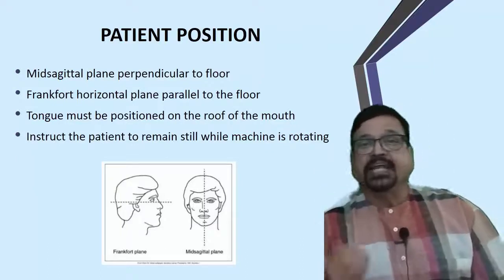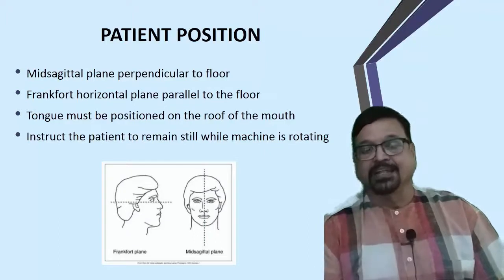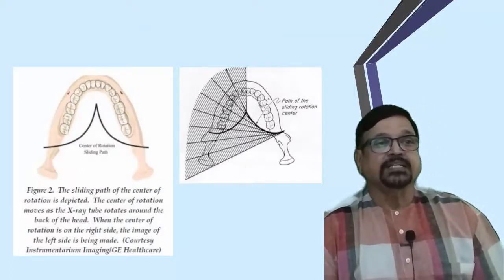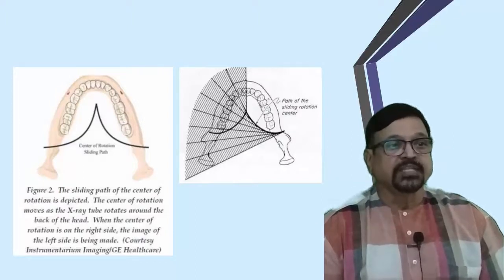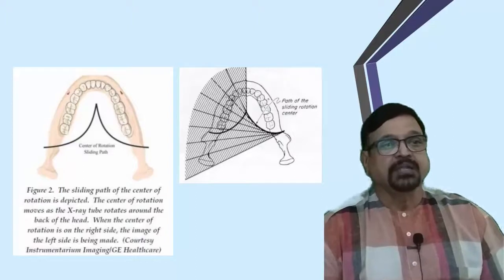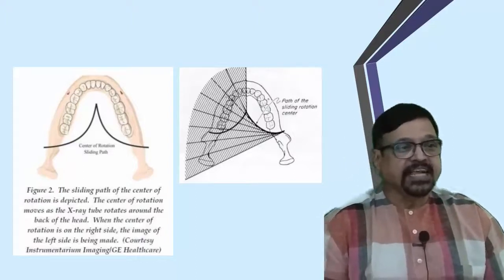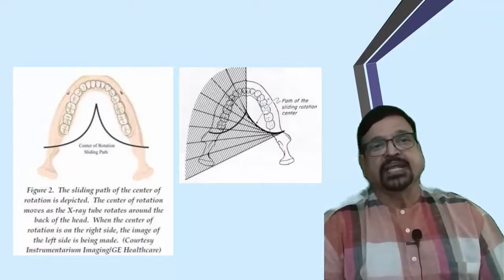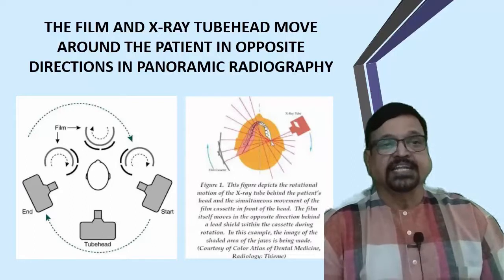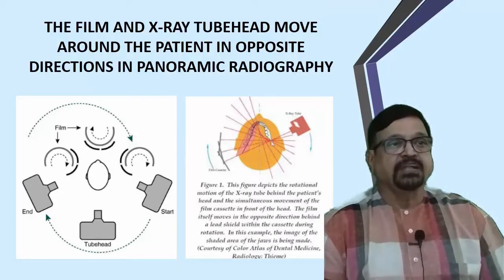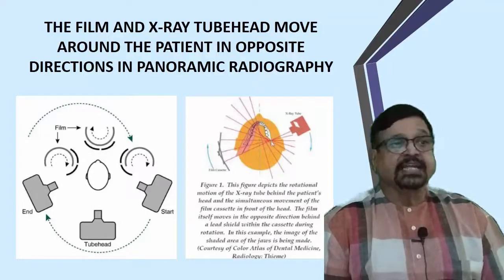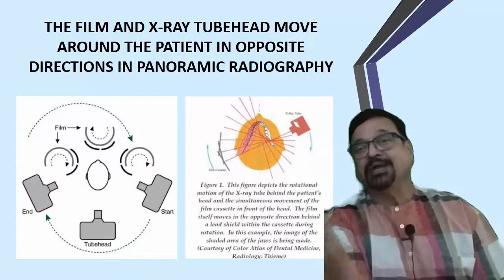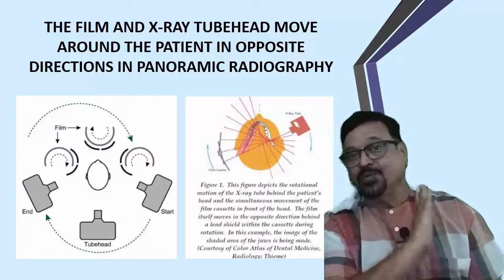The patient must be instructed to remain still - the machine is rotating and as long as it is moving around the head, the patient should not move. If the patient moves, object A, B, C, D will shift and get blurred. The center of rotation moves as the tube rotates around the back of the head - when the center of rotation is on the right side, the image of the left side is being made. Not all structures get focused; only the teeth at the periphery get focused while those at the center are unsharp.